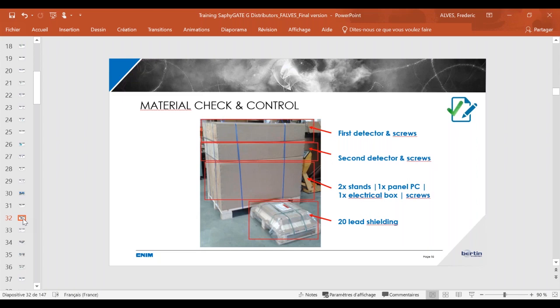You will normally receive the material as shown here: a packaging with the first detector and its associated screws, then a second packaging with the second detector and its associated screws. A third one with the two stands, the panel PC, the electrical box, and screws. And the last packaging is the lead shieldings, 20 total, 10 per detector. Be sure you have all the necessary material before starting to install it.